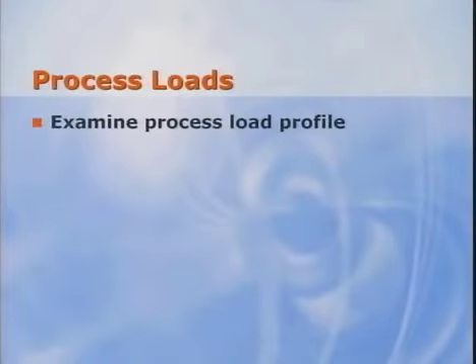Within an industrial or commercial setting, there is often a need for process heat. Some possible uses are to make materials more malleable or to keep product at a specific condition while it cures. Quite often, these process loads require a constant or near constant temperature. Here's some general guidance on providing waterside heat recovery for these loads. First, look at the process load profile.